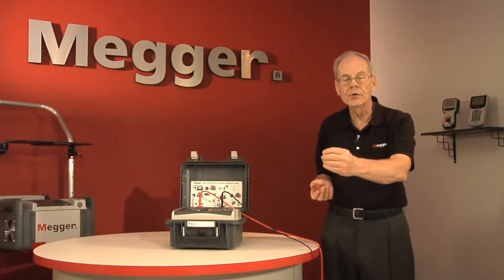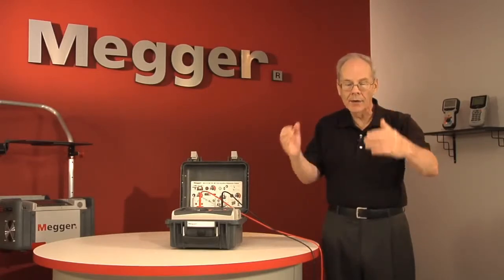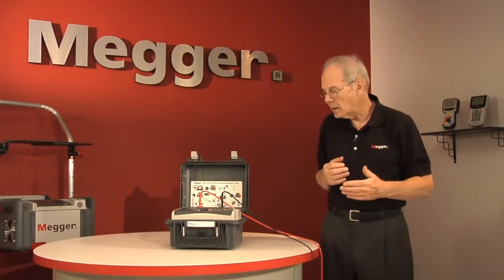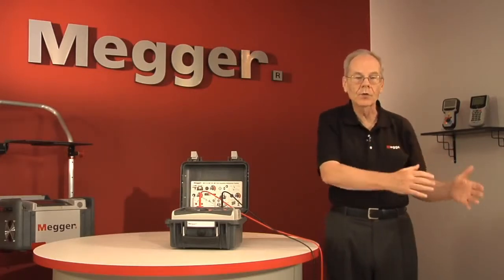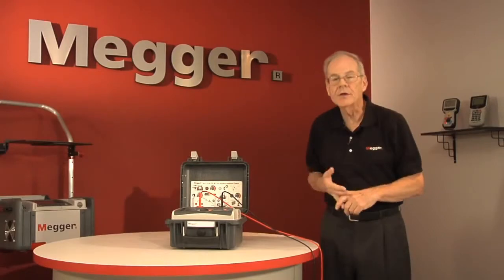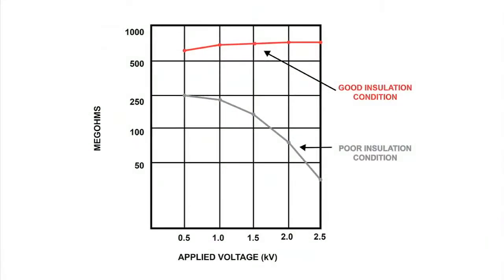You can look at your values at each minute and compare then the changes of resistance with voltage increase. And the critical factor here is that good insulation should stand up to changes in voltage with relatively little difference. But deteriorated insulation, every time the voltage is increased, more flaws will be brought into operation in passing leakage current from one terminal to the other, and so your resistance values will drop incrementally each time you've increased the voltage.